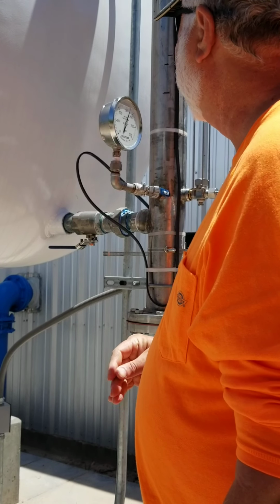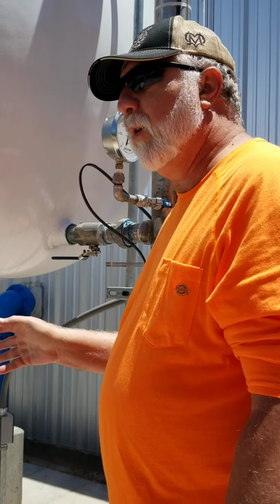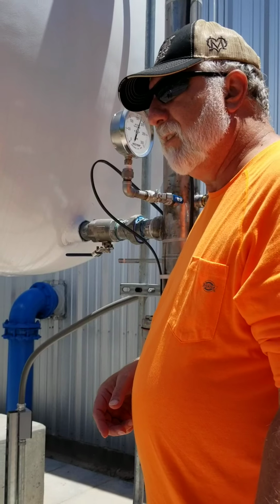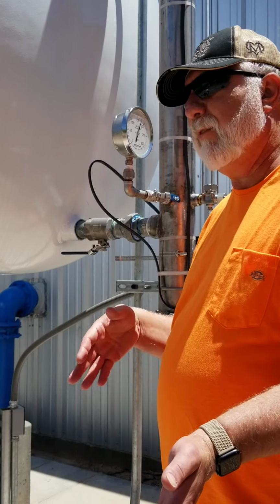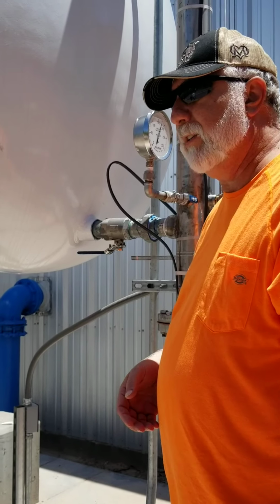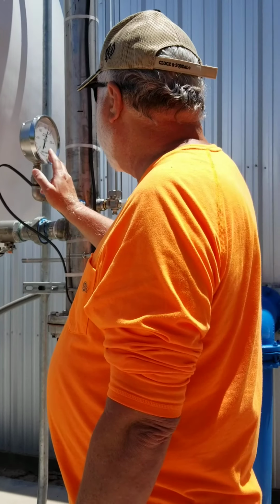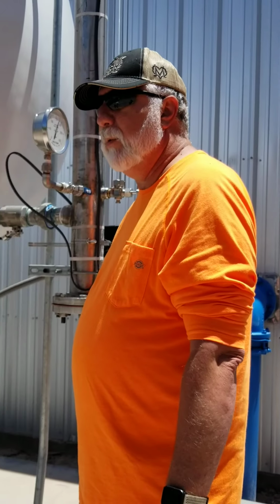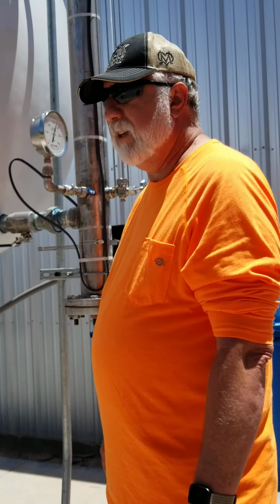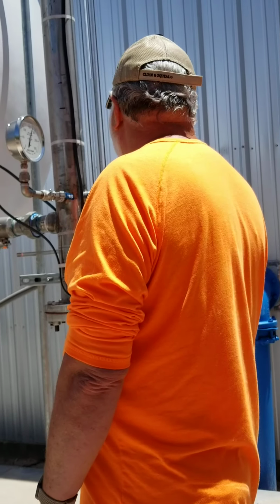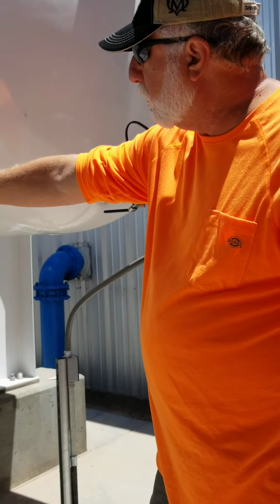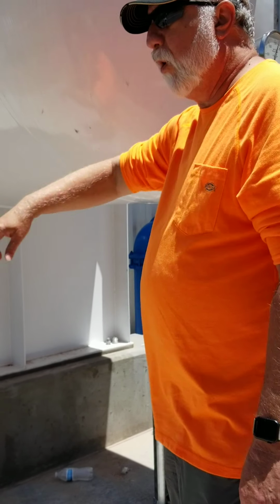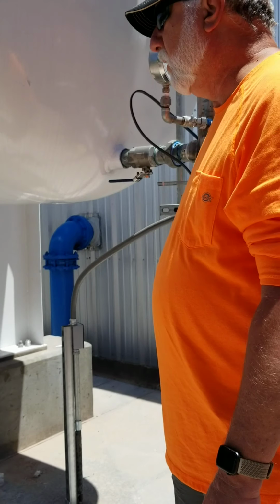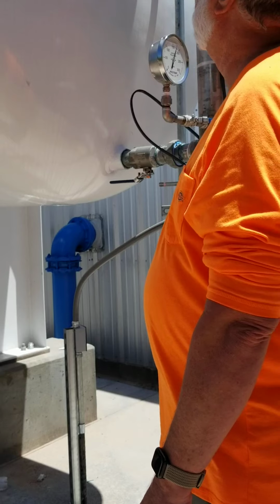Your system, I don't remember what they said it was, and I'm sure they'll go over that when they go over the controls. It's like 165 to 185 is what pressure range you're going to run. You have a mechanical pressure gauge here, which is going to tell you quick visual indication if you didn't have power for any reason. You have a pressure transmitter underneath that reads back to the control panel, which is looking at the system pressure.